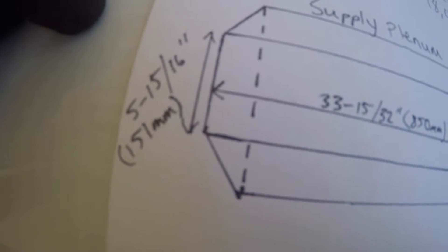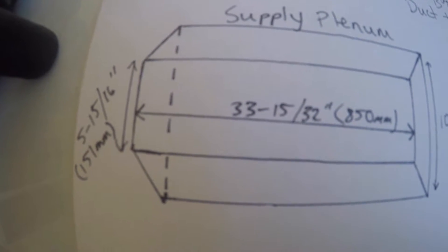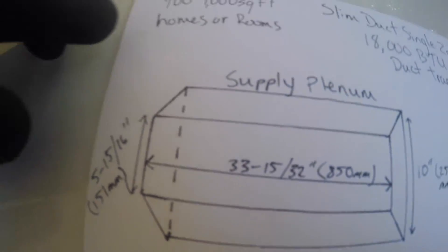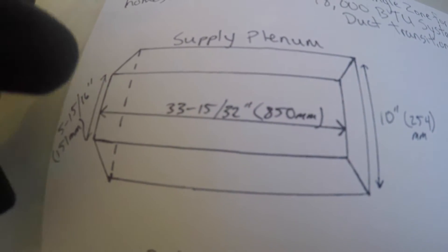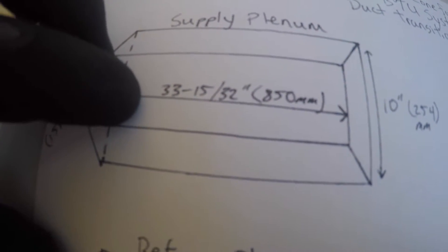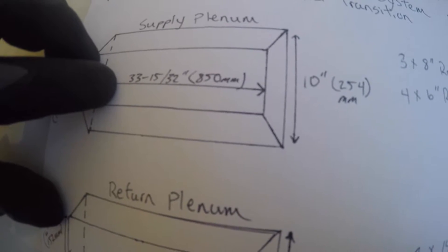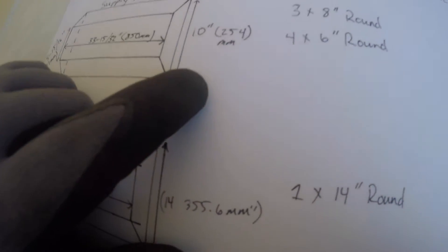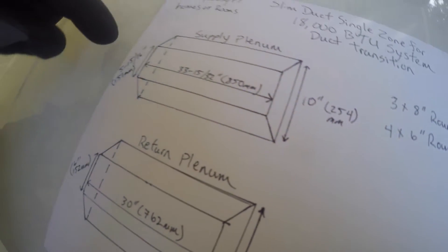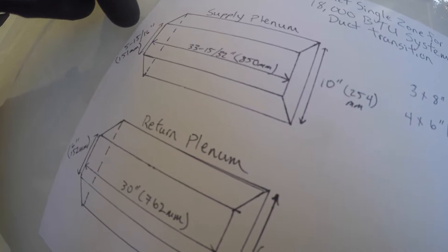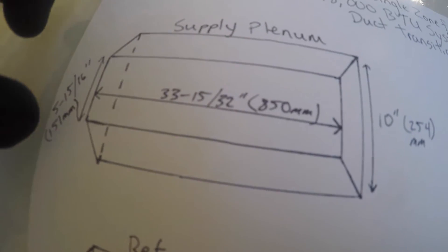we're at 5 15/16 inches, which is 151 millimeters high on this supply connection, and we're looking at 33 15/32 inches, which equals 850 millimeters. What would work for this system is a 10-inch transition.